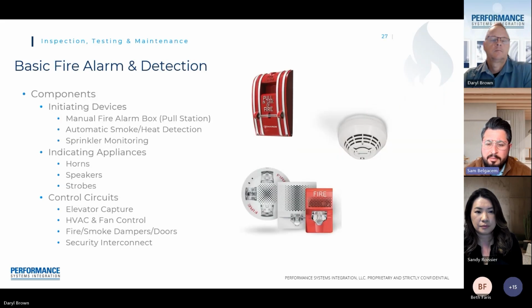So the detection devices, also called initiating devices, are either manual or automatic. These are considered the input information to the fire panel, and then the output information goes through the indicating appliances or the notification, like a horn or strobe. In the event of fire, the control panel will also recall the elevator, as well as block the smoke by closing the fire door, and then trigger the smoke damper in the HVAC system to prevent the smoke from spreading.